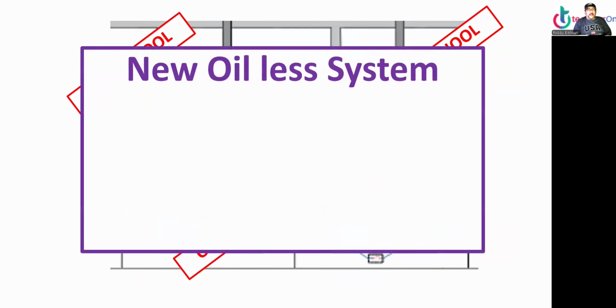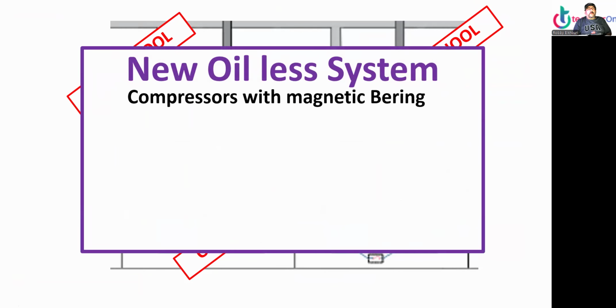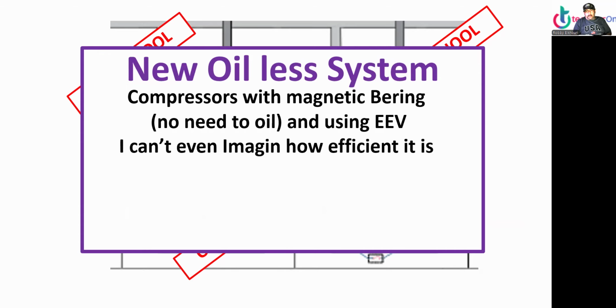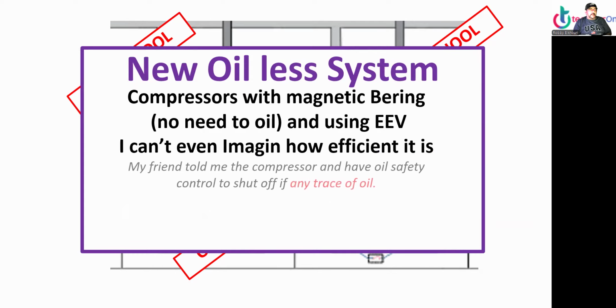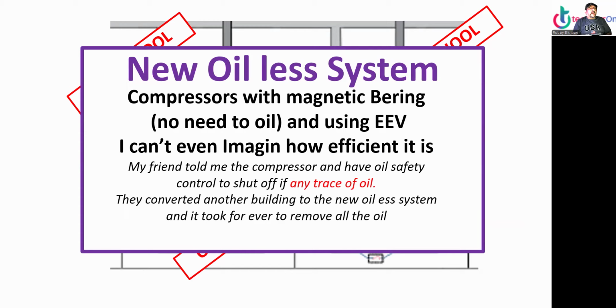Now we have the new oil-less system my friend told me about. Compressors with magnetic bearings, no need for oil. And of course, using an electronic expansion valve. I can't imagine how efficient it is. My friend told me the compressor has an oil safety control to shut off if any trace of oil. How you like that, huh? New technology. He converted another building to the new oil-less system, and it took forever to remove all the oil. He told me the compressor keeps shutting off on oil safety, too much oil in it, any trace of oil in it. So it's amazing how much oil there is in the system. This is the new technology moving on.